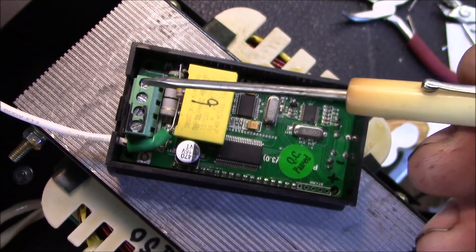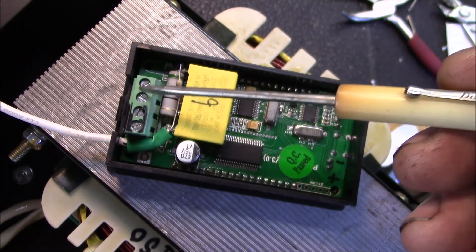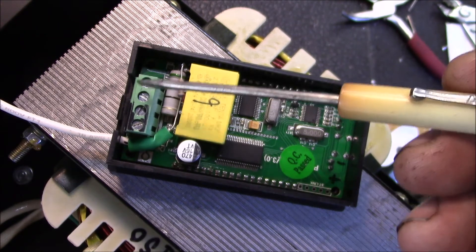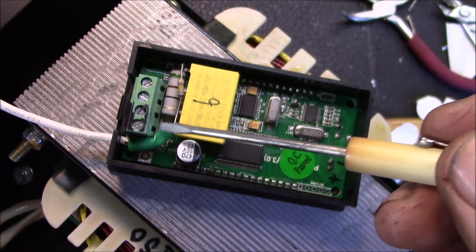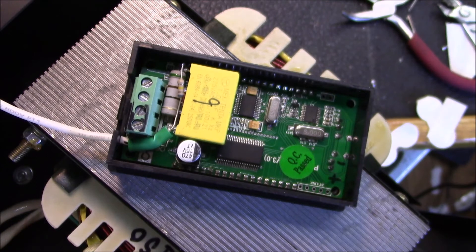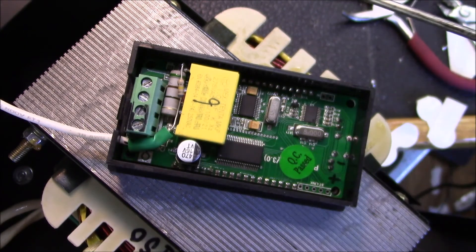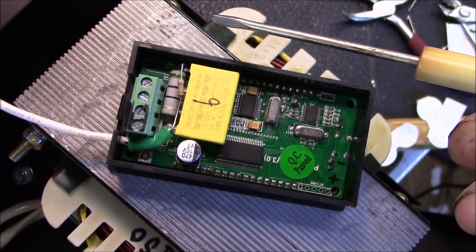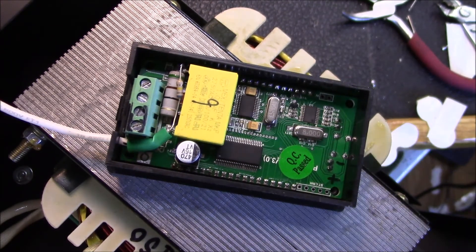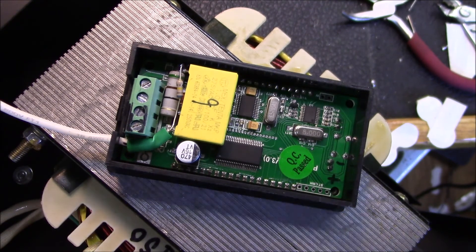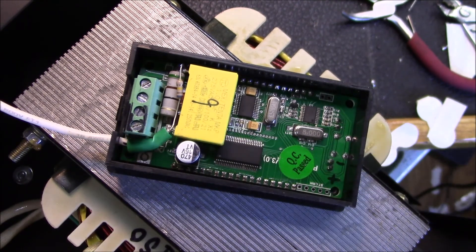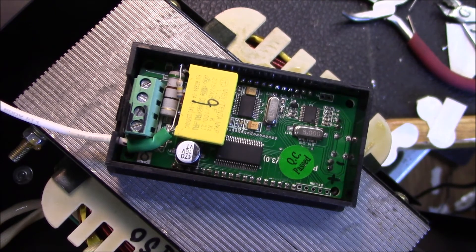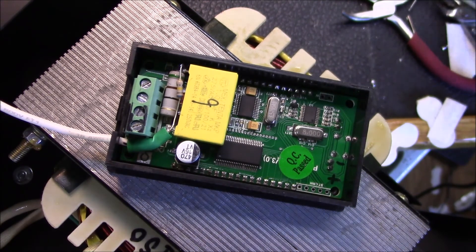The only complication of doing that is when you separate these wires here, you've now defined this wire as the line voltage and you've defined this other side here as the neutral side of the connector. If you don't separate this wire out, it really doesn't matter—it's AC voltage, you can call one side line and the other side neutral. You've got to make sure that you keep track of which side is switched, because once you do that, you've made that distinction.